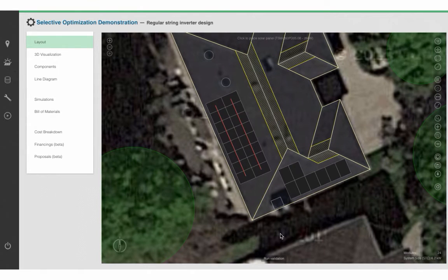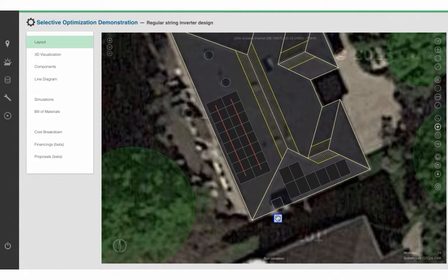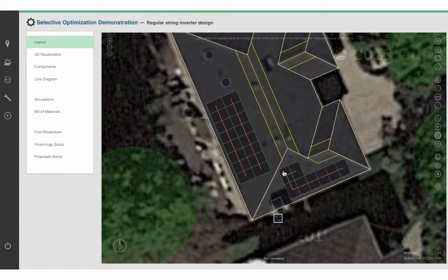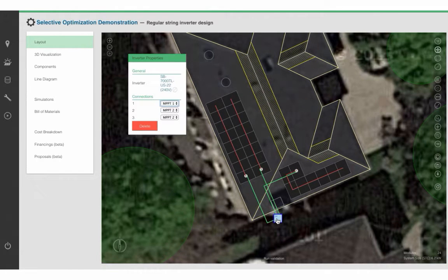Now I would like to select an inverter. I'll click Add Component, select an inverter — in this case the Sunnyboy 7000 TL — and place it down here. To finish this off, I'm going to string my modules. It lights up in red when you're outside the acceptable input voltage range of the inverter, and turns green when you're within it. Then I am going to connect my strings to the inverter. Aurora is smart enough to automatically connect the two strings on the west side of the roof to one MPPT of this inverter, and the other string to the second MPPT. And if I right-click on the inverter, you can see that's exactly what it did.